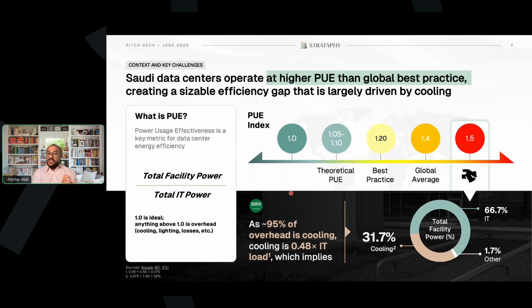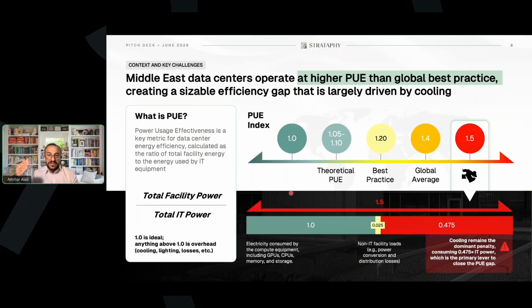Now, let's go back to the PUE. Higher is bad, 1 is perfect. Where is this bad above-1 number coming from? The majority of it goes to cooling. When you look at a PUE higher than 1, you have some facility loads, conversion and distribution losses, which could be 0.05 all the way to 0.1, but the remaining is cooling. The lighting and everything else you have in the system is very minimal. Cooling comes at a significant cost.